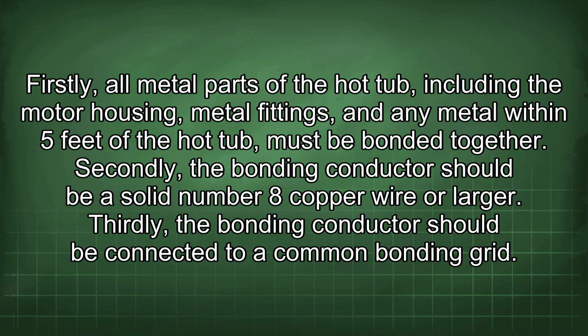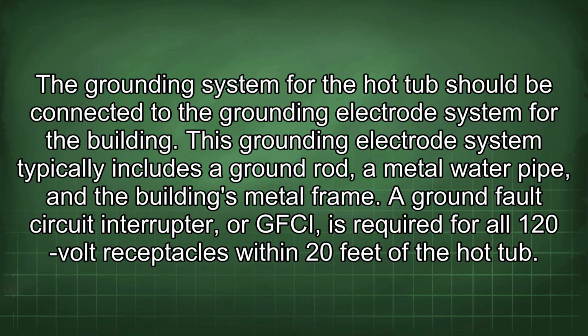Secondly, the bonding conductor should be a solid number 8 copper wire or larger. Thirdly, the bonding conductor should be connected to a common bonding grid. The grounding system for the hot tub should be connected to the grounding electrode system for the building. This grounding electrode system typically includes a ground rod, a metal water pipe, and the building's metal frame.